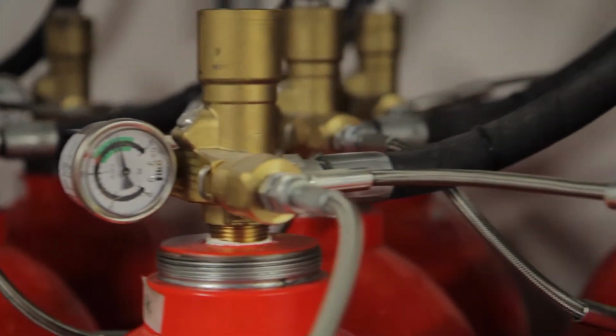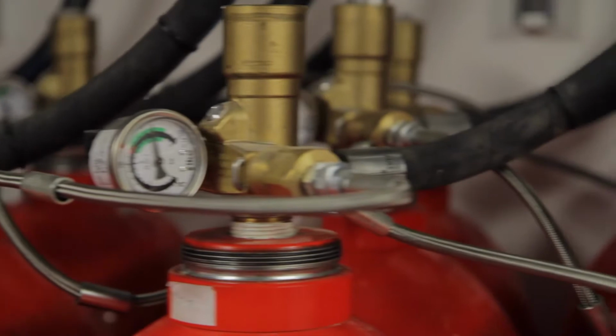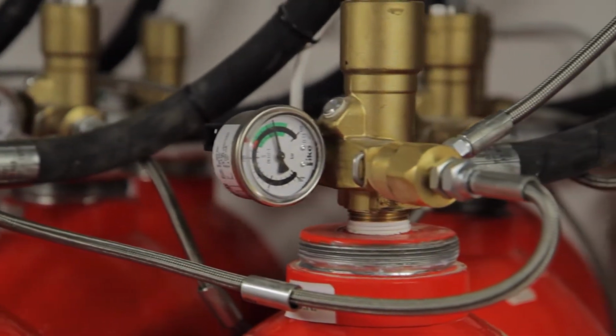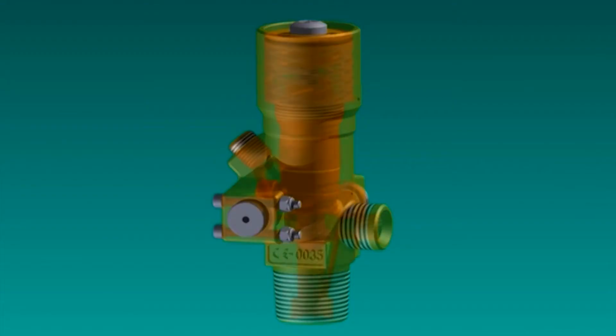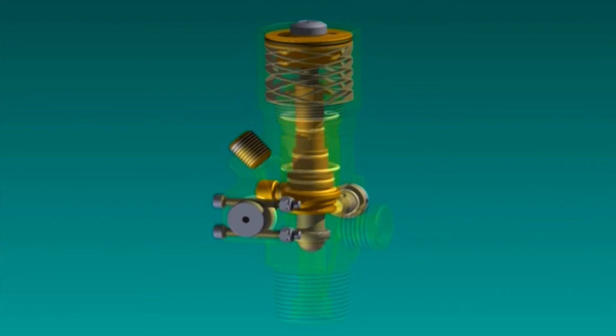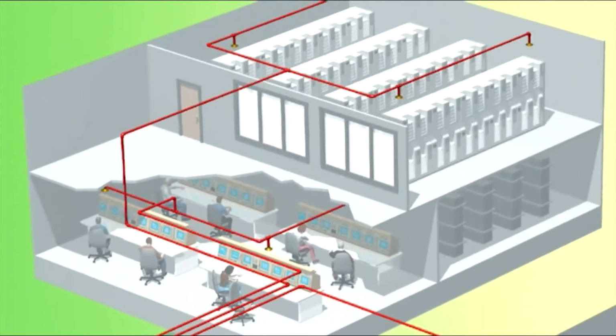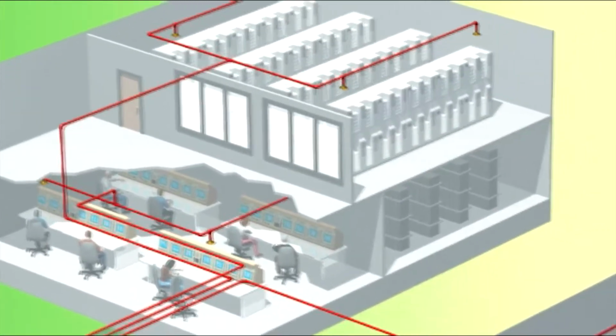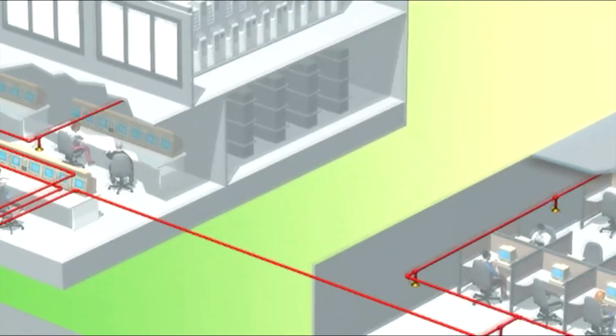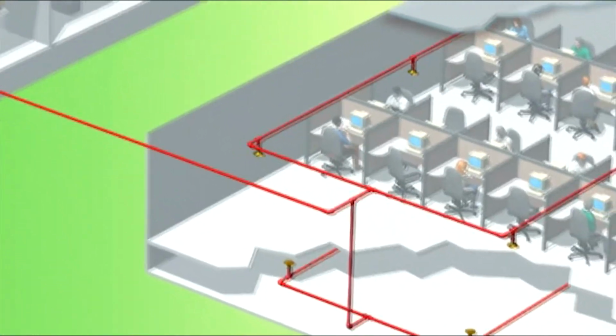This safe and controlled process is made possible by Fike's unique Pro Inert valve, which reduces the pressure in the cylinder from 300 or 200 bar to just 42 bar. This means lower capital outlay, smaller bore pipework, lower installation costs, and lower maintenance costs.